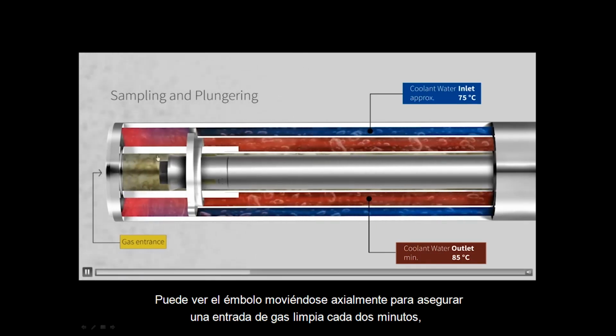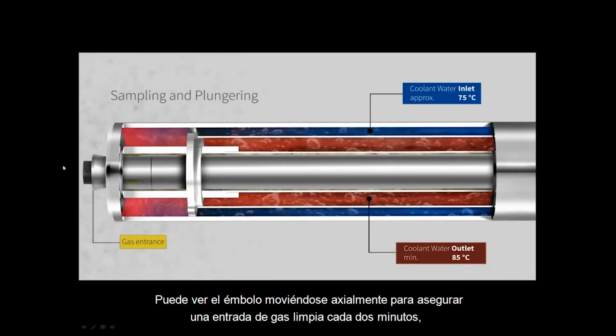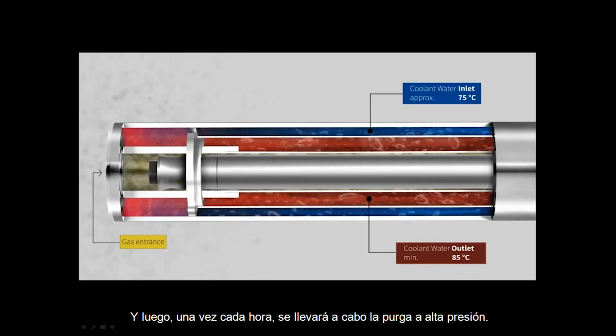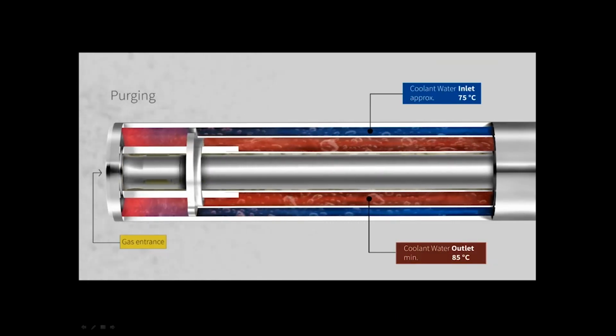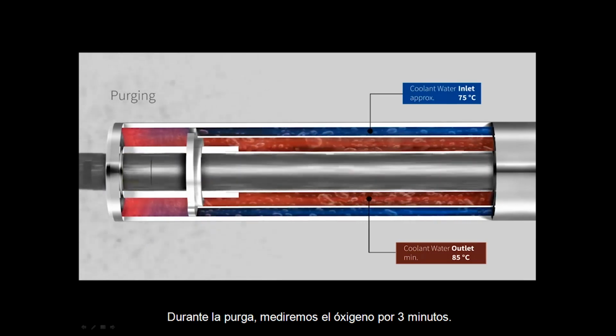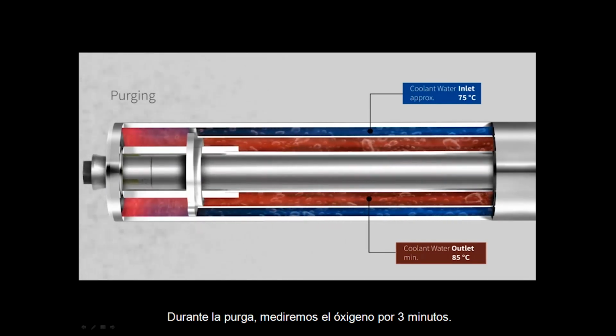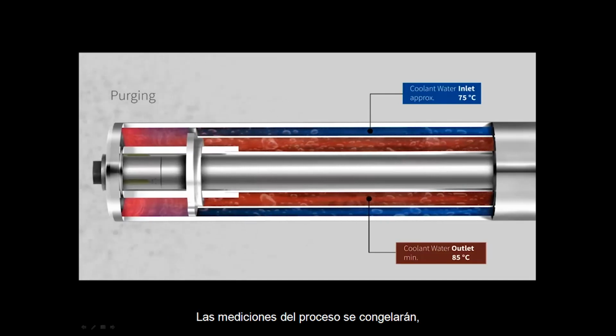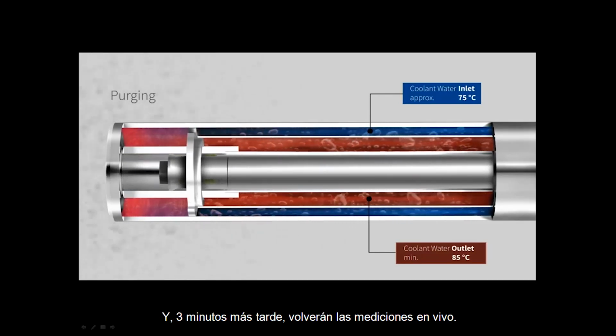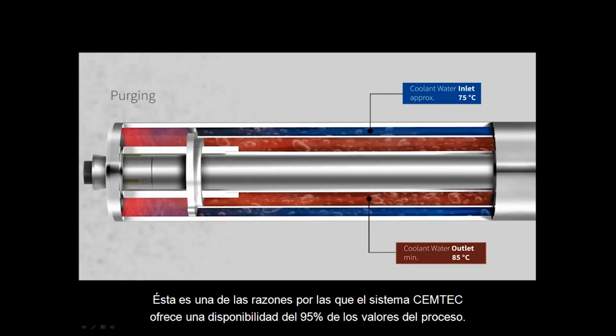You can see the plunger moving to ensure a clean gas entrance every couple of minutes, and then once every hour the high pressure purging will take place. During purging, we will measure oxygen for 3 minutes. Process measurements will be frozen, and 3 minutes later, live measurements will take place. This is one of the reasons why the CEMTEC system offers a 95% availability of the process values.